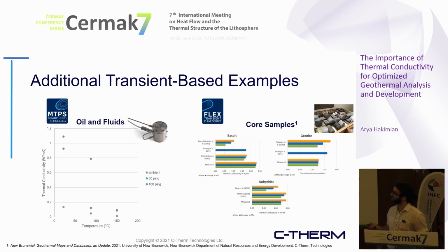The image on the right is just some of the data that was collected in conjunction with that previous study I mentioned with the University of New Brunswick, C-Therm, and the local governing bodies of New Brunswick, taking a look at how these different materials can be measured. Depending on the data that you're comparing to, understanding the method that was used, it's always good to get a baseline and understand the overall performance of these samples, and ensure that if you are comparing to previous data, there is correlation there or you understand where these differences can come from.